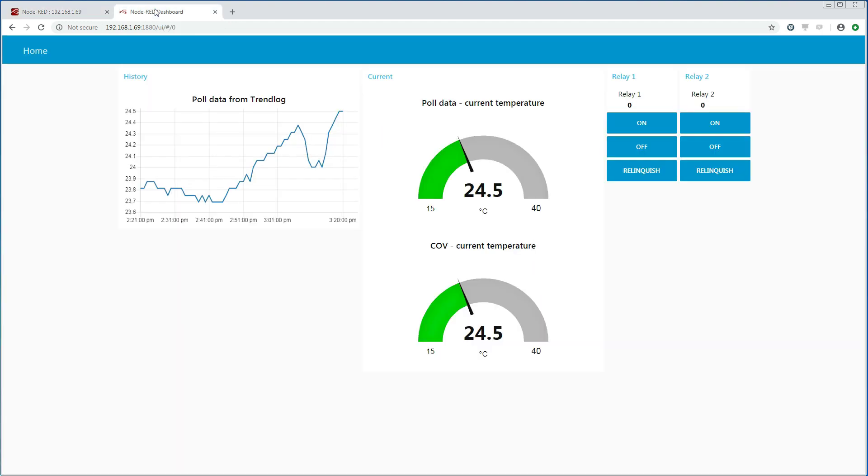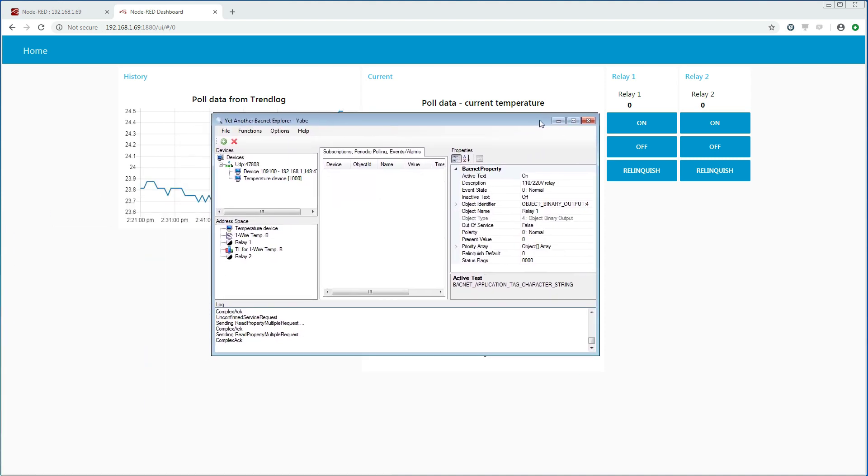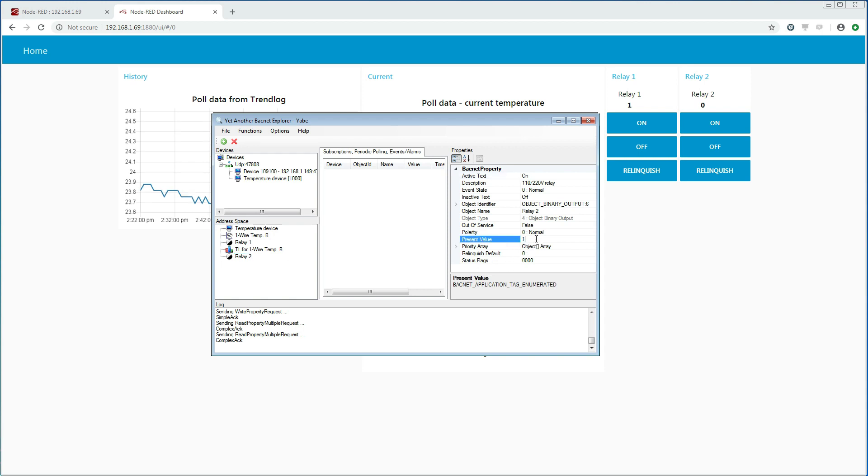If we go to the dashboard we see these two text nodes here. And we see that both relays are off. I will now drag a BACnet explorer onto the screen. I will find relay 1. And we see also here that the relay is off. Now let me turn the relay on by setting the value to 1. And we see in the dashboard behind me that relay 1 changes to 1. Let me do the same for relay 2. So we see that the COVs are working for the relays.